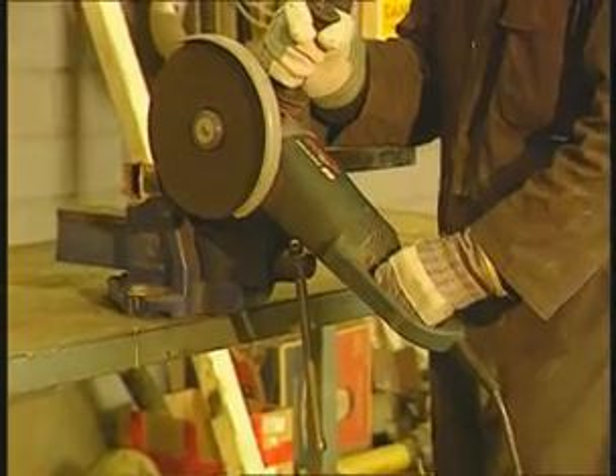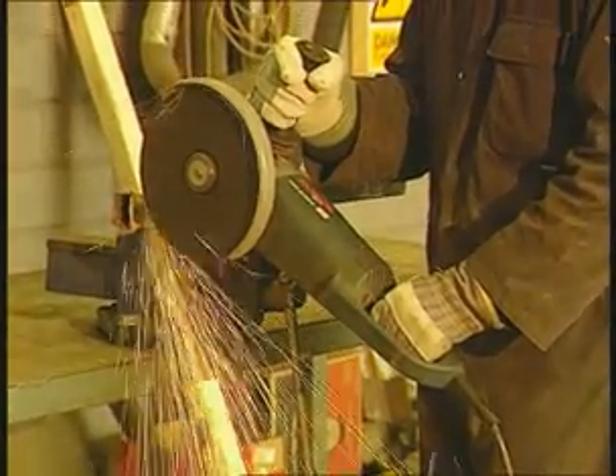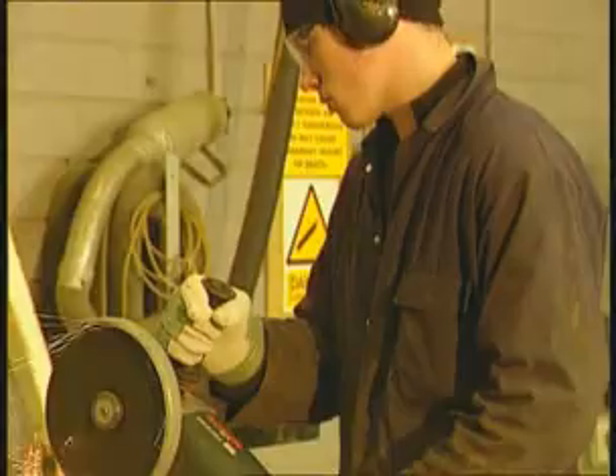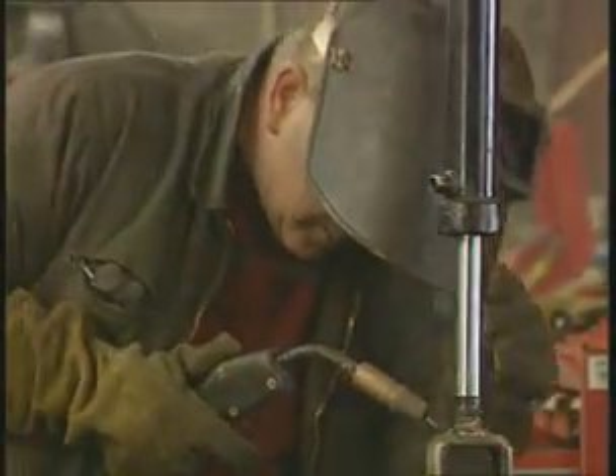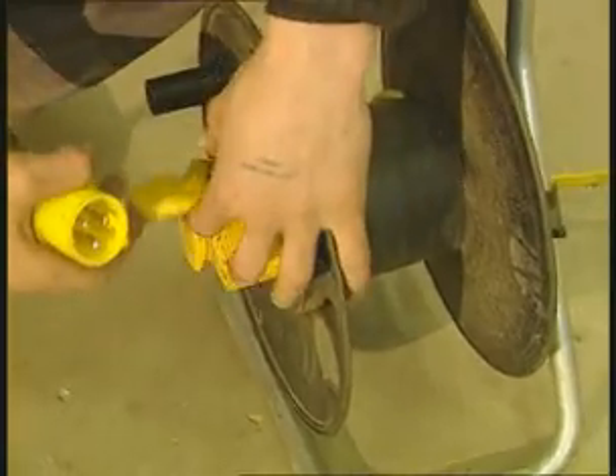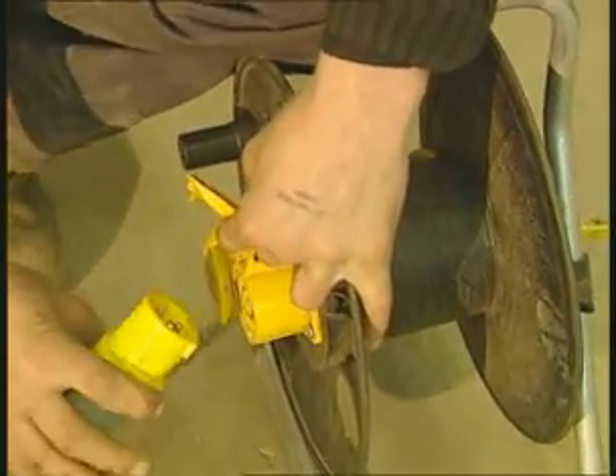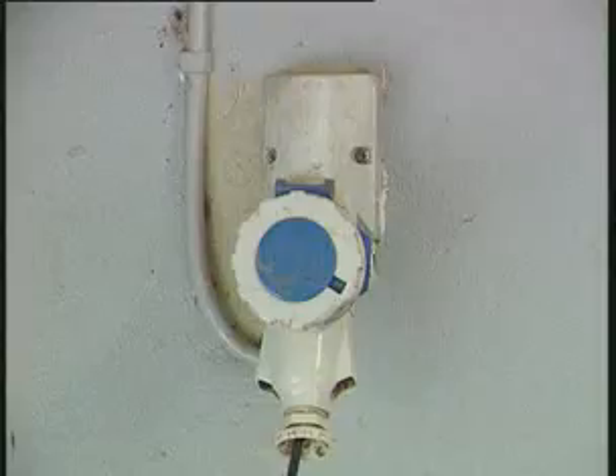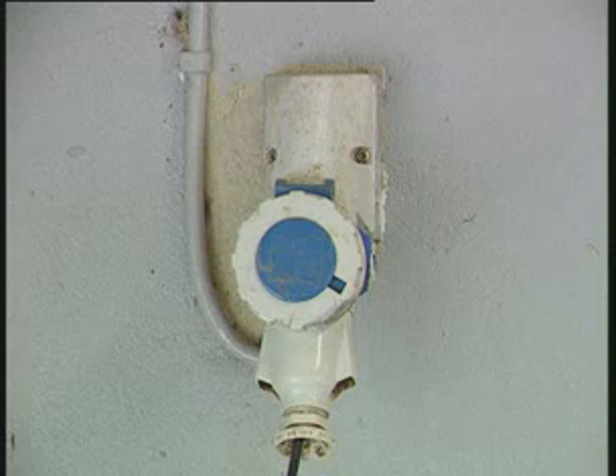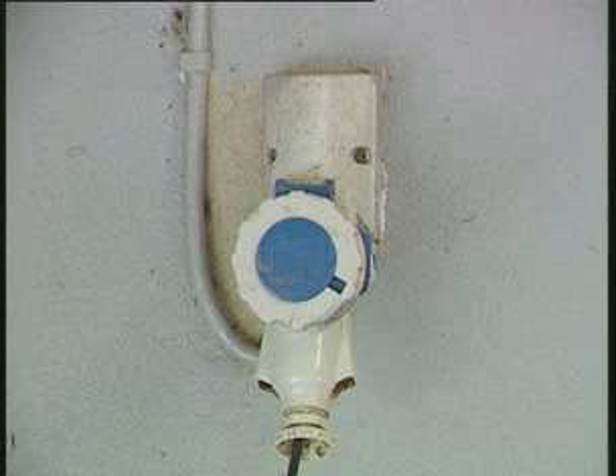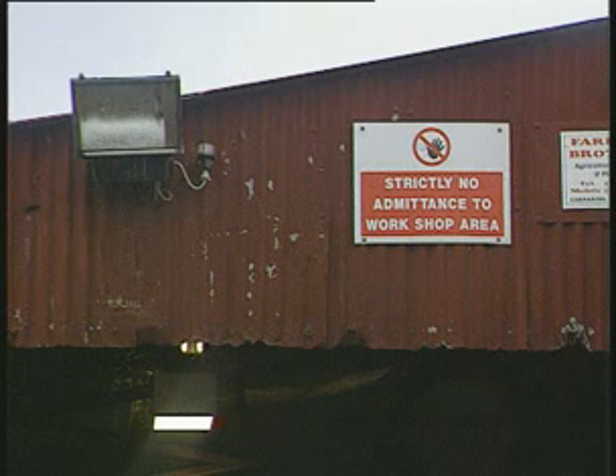The 16 amp size will supply most portable tools, but the larger 32 amp size should be used for electric welders. Plugs and sockets for use in areas likely to be hosed down must have a higher degree of protection against water, IP55. Outdoor floodlights on farms will be subject to severe weather conditions, and a protection rating of IP55 is recommended.